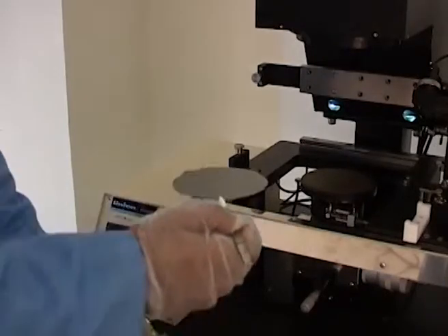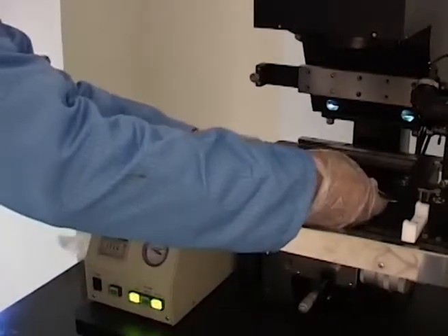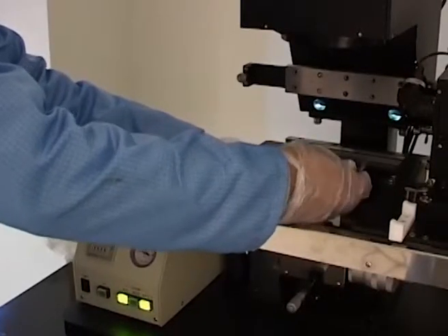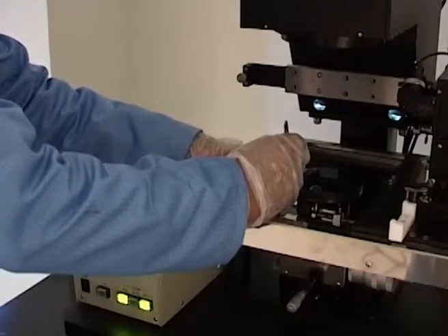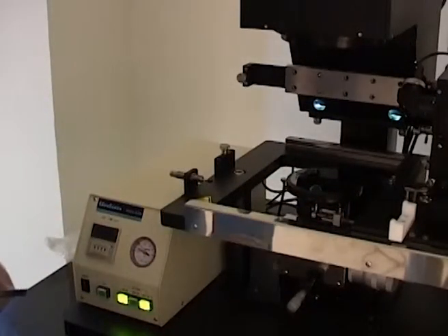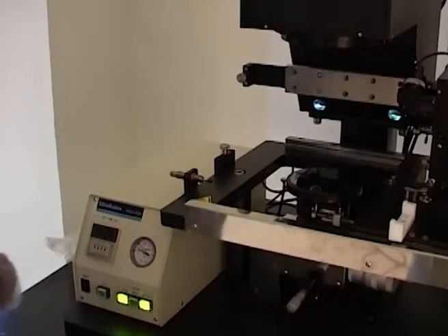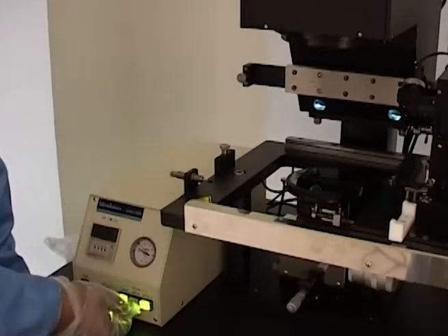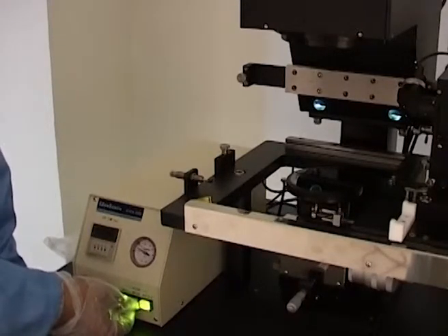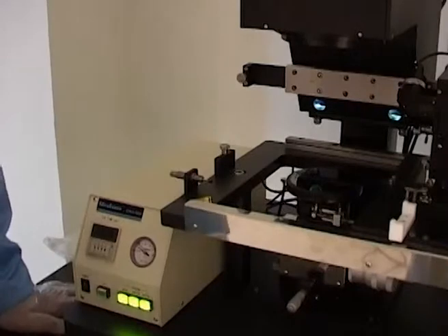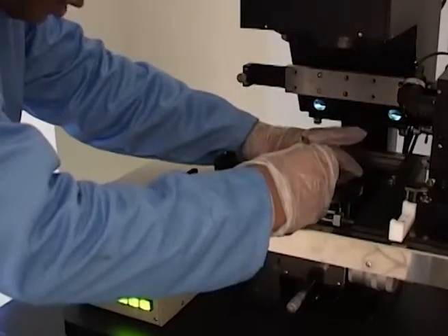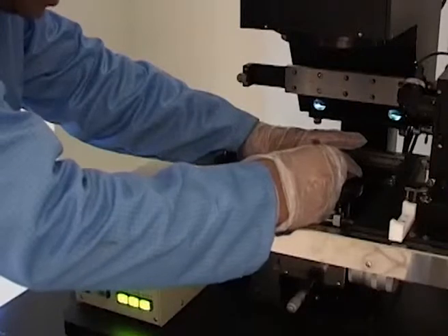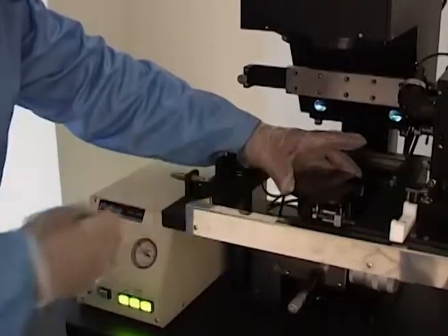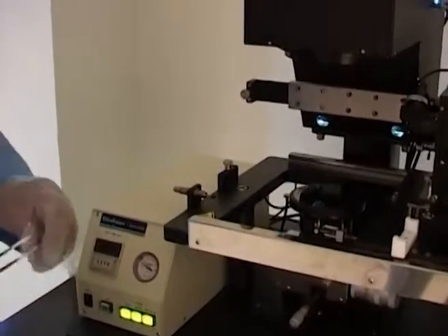Essentially now we are going to take the wafer from its box and put it in this particular zone here, which is meant for wafer holding. Again, we would like to use vacuum as a means of locking this wafer, the spun coated, resist coated wafer, onto the exposure stage. And this switch right here, which says wafer vacuum, ensures that the vacuum is used to pull and lock the wafer. I want to check whether the vacuum is working well, and I found out that it doesn't move anymore. The wafer is jammed with respect to the stage, and the next step is exposure to UV.